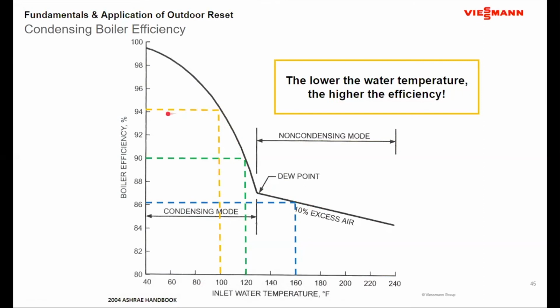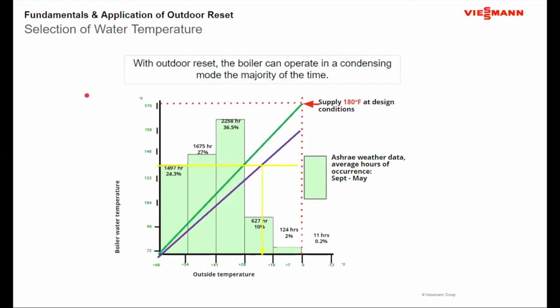So these numbers here, this 94 number, that is an achievable number with air handlers and also with baseboard. And the thing is, when I start to do an existing building, a lot of times the argument says, if I do an existing building, I'm going to do a condensing boiler, but I'm not going to get much efficiency out of it because of the required water temperatures. If you do outdoor reset, that relationship can change. So here we're looking at the ASHRAE data for Boston, Massachusetts.